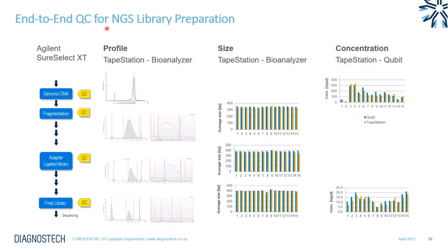To wrap up, the TapeStation is really an end-to-end QC platform. It can measure input genomic DNA going into the assay, assess fragmentation as you work through the workflow, evaluate adapter ligation efficiency by looking at the size shift on the electropherogram as well as the presence of any adapter dimers, and finally for the final library — vital to QC before sequencing — it measures size and provides the average fragment size for molarity calculations. Although the Qubit is still recommended for double-stranded DNA quantification, you are able to get quite similar values off the TapeStation, making it a one-assay-for-all approach.